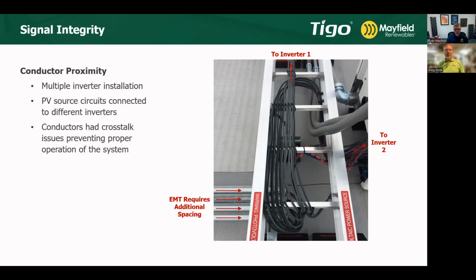So I'm just thinking, had they had the right training and known about this being an issue—if those top two pipes are going to inverter 1 and the bottom two are going to inverter 2—they probably could have separated them out at the array, kept them on either side of the walkway. You can see there's a walk path there. I kind of remember this site a little bit. They could have kept those on opposite sides of the pathway, that would have been fine, then come to that cable tray at opposite ends, and they would have been probably more than fine.